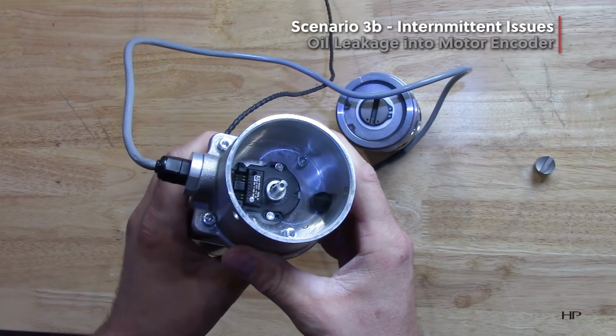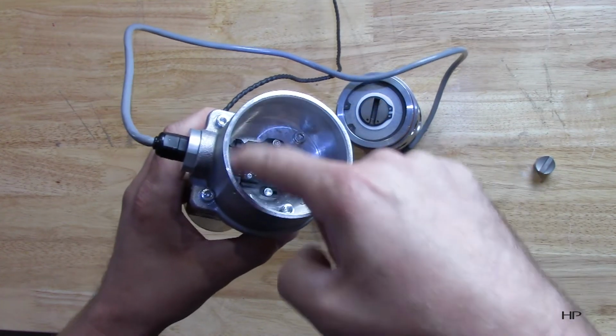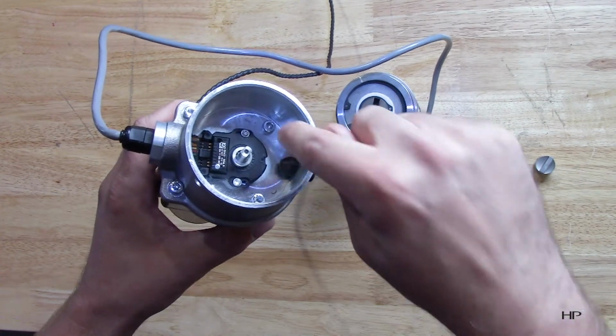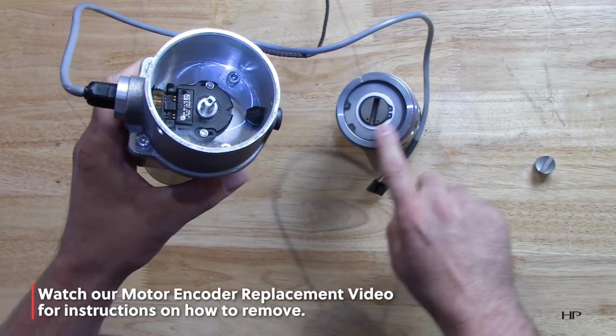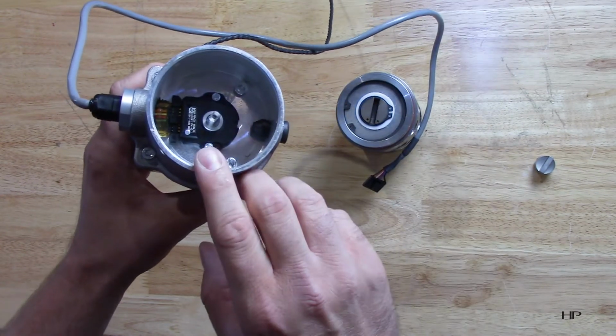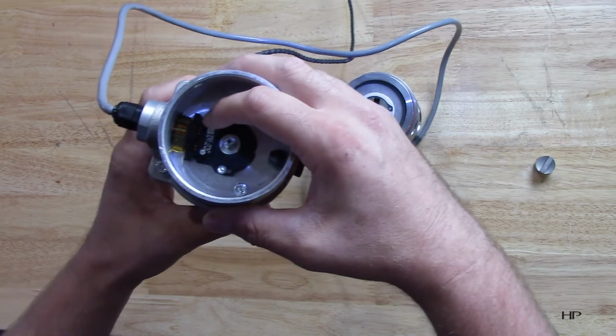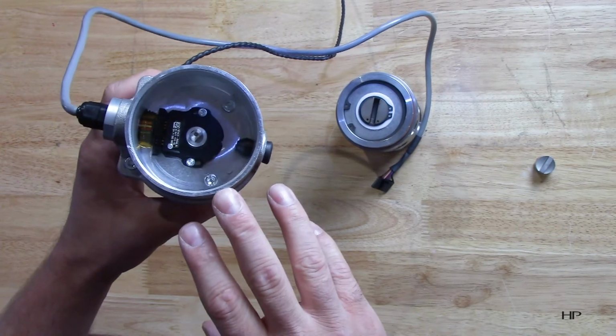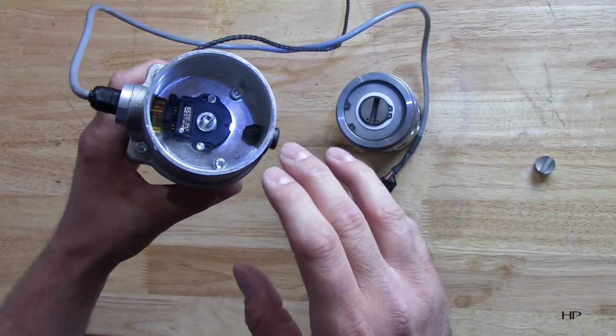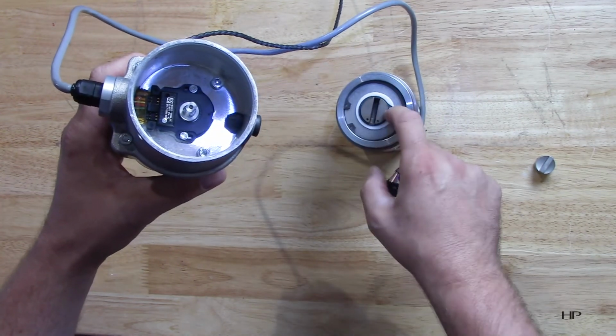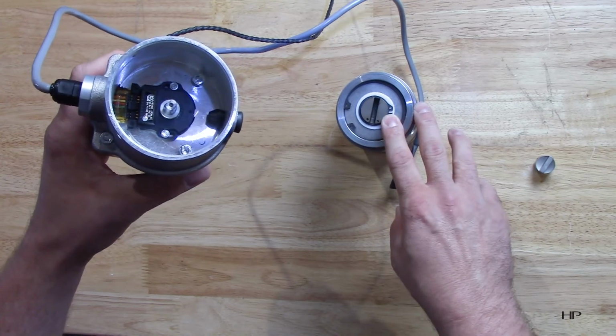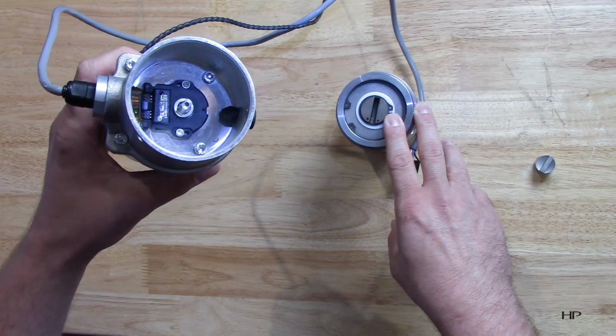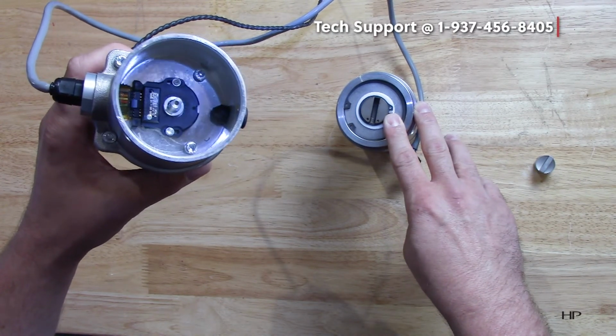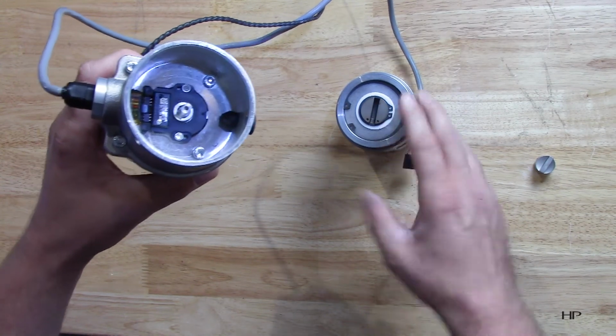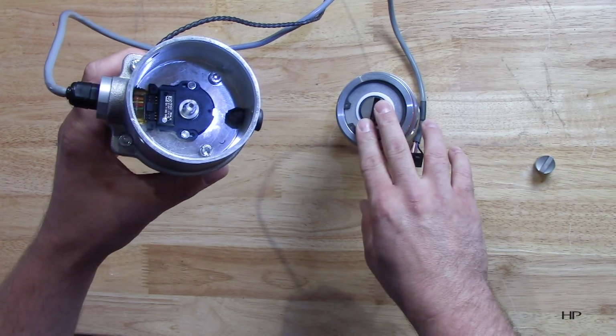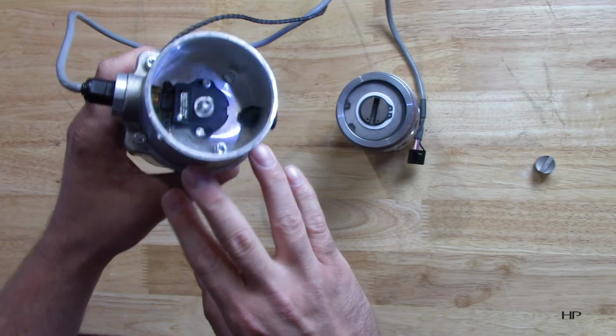When we're talking about intermittent issues with an E82D, if we have any oil residue whatsoever when we separate these two components, either inside this cavity or housing or on top of this selector valve body, this would end up causing an intermittent issue with the E82D, especially if that oil is to get on the encoder assembly here. Now, if we're in the field and we see that this unit has indications of oil leakage, which would be from this seal here, which unfortunately is not a serviceable seal, you're going to need to call into tech support, take a couple pictures and send them, and then they will review it and give you approval to replace this entire assembly. Because if we have oil residue in here or in here, replacing the encoder motor is going to be a very temporary solution.